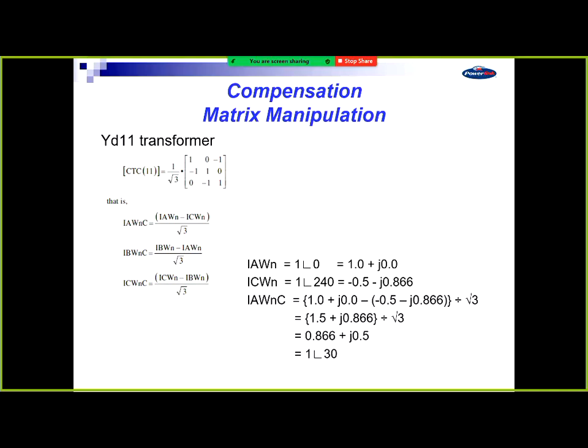on the LV side. The one is, look, the ratio, you've got to have CT ratios in there as well. That's a separate sort of equation which gets done. This sorts out the zero sequence and the phase shifting. Another little compensation formula in there needs to work out the mismatch in CT ratios for the transformer. So that's basically how they're doing it.